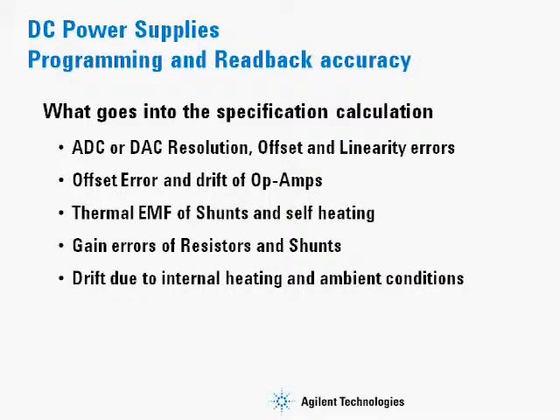When calculating the accuracy of a power supply for both programming and readback, many things are taken into account in the calculations.